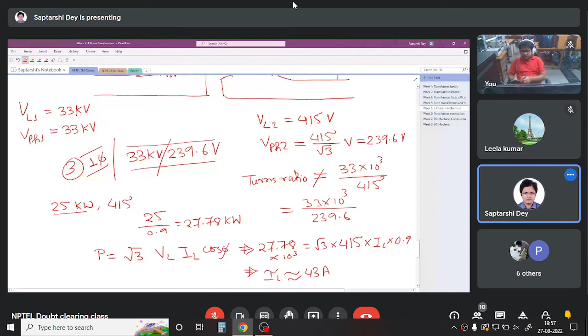Anyway, now we look at the questions. The first question says, estimate the minimum required kVA of the transformer. We have found out that 27.78 kilowatt is the active power, P, that the transformer is supplying at a power factor of 0.9. Now we have to find out Q.